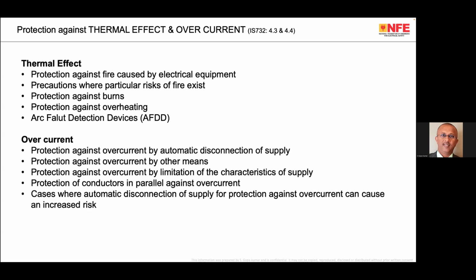There is one more subject, overcurrent. Overcurrent also creates a thermal effect. An electrical installation, as a mandatory requirement, needs protection against overcurrent. So here the safety measures are protection against overcurrent by automatic disconnection of supply, and protection against overcurrent by other means. There are various means, for example limiting the current: once there is an overcurrent, the source itself is designed in such a way that the current is limited to less than a certain amount. Others are protection against overcurrent by limitation of characteristics of the supply, and protection of conductors in parallel against overcurrent. So basically, there are two subjects, thermal effect and overcurrent. Today, we are going to talk only about thermal effect, and I will be focusing more on protection against fire caused by electrical equipment.